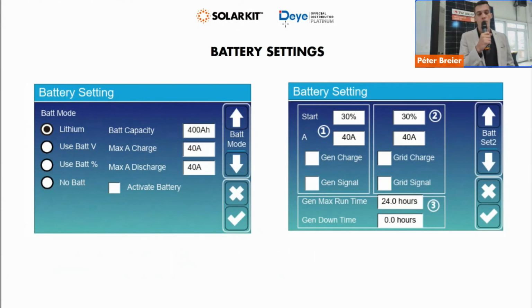On the second page, if you go one page down with the arrow on the right, then you will see 2 charge possibilities. Basically, if you want to charge the batteries with the generator, or if you want to charge the batteries from the grid. From the grid, I think you should be allowed to charge. I mean, you should allow that option, but you should reduce this percentage to around 5% to make sure if the battery drops down to 5%, it will start charging from the grid. So you can avoid many malfunctions with that option.